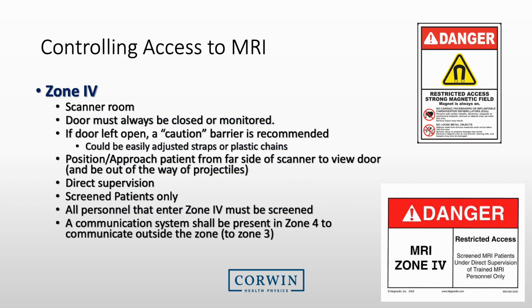Zone 4 is the most hazardous area in MRI. It is the scanner room itself. If Zone 4 is directly accessible from Zone 3, try to keep the MRI door monitored at all times. Close the door whenever you enter. Try to position the patient from the far side of the scanner so that you can view the door. Ensure that only screened individuals access this area, including staff. A communication system shall be present in Zone 4 to communicate to those outside Zone 4 to those within Zone 3.